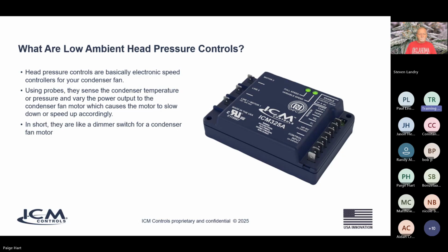So what are low ambient head pressure controls? Low ambient head pressure controls are basically electronic speed controllers for your fan. They use temperature probes or pressure transducers that sense the condenser temperature or pressure in the system and vary the output power to the condenser fan motor to slow or speed up the fan motor. By doing this, we can control how much air is going past the condenser coil, which then maintains our head pressure in very low temperatures. Now, we'll get into why that's important in the next few slides.